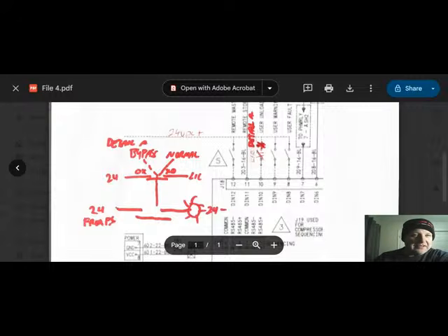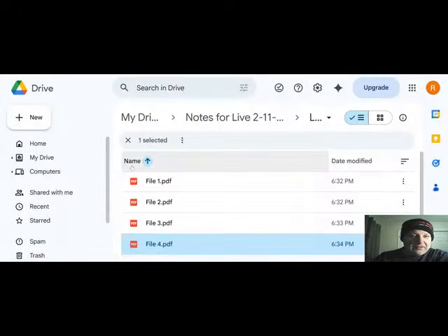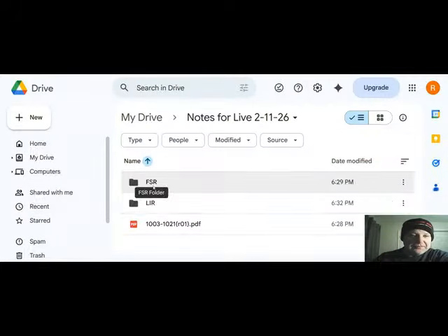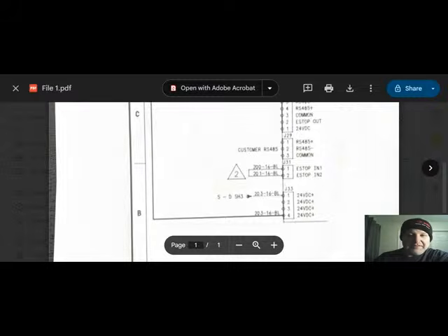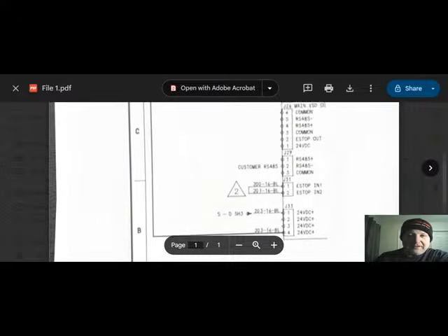The other example I shared in the original post was if you are going to tie an emergency stop circuit into the fire suppression relay. Not all compressors have this, but on the Solar, if we are lucky enough, we have a secondary e-stop input. You could do this just as easily, interrupting your regular e-stop circuit as well. You just have to know if that e-stop faults on an open or a closed, and you can set your wiring up accordingly. But we have a secondary e-stop input here, so that's what we are going to use.